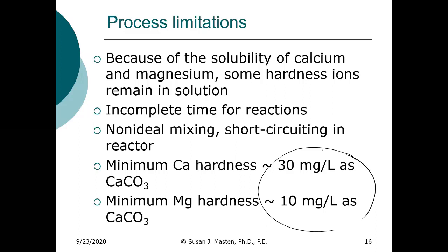And that's because, one, the solubility. The other thing is that solubility reactions are not rapid. It's unlike an acid-base reaction, which is almost instantaneous. Solubility reactions are time dependent, and there may be incomplete time for a complete reaction to occur within the flocculation basin. There's also non-ideal mixing. We've talked about that. We've talked about short-circuiting. I mentioned that, and that can result in process limitations.